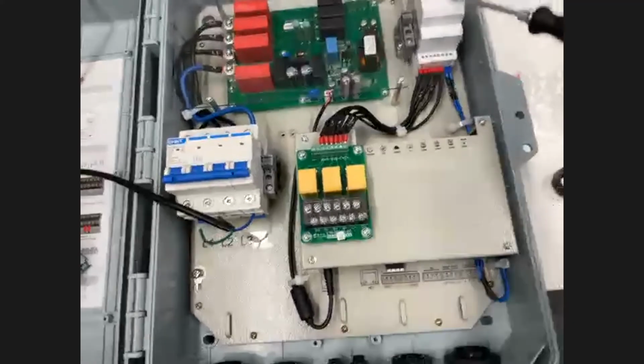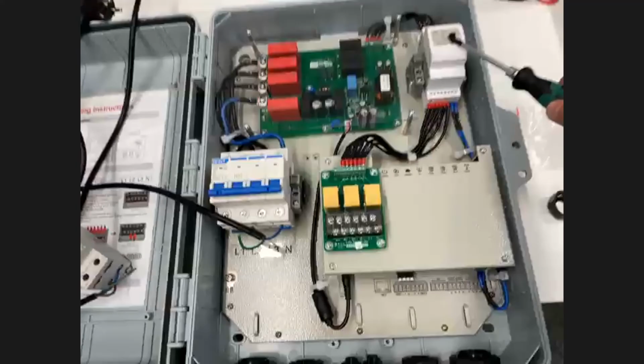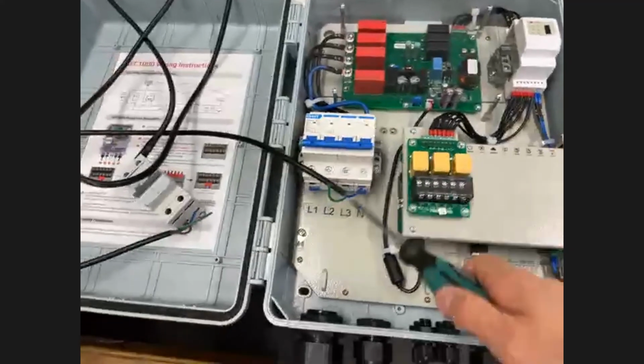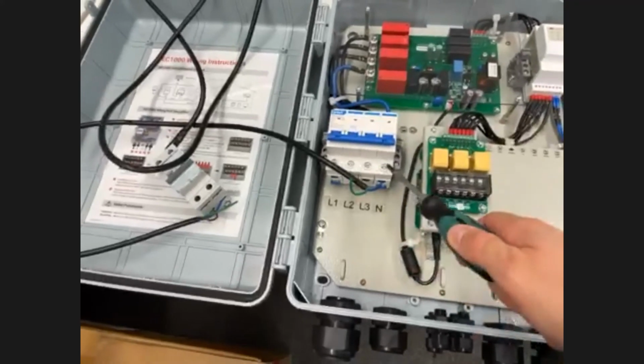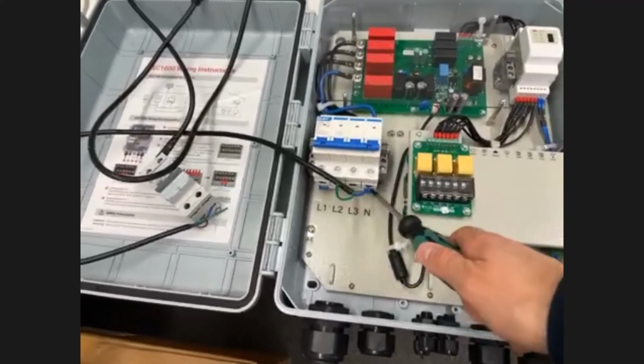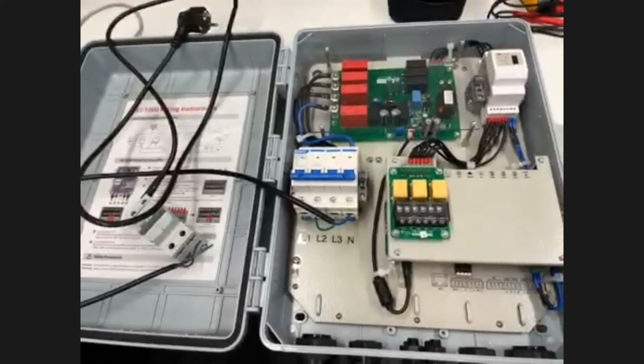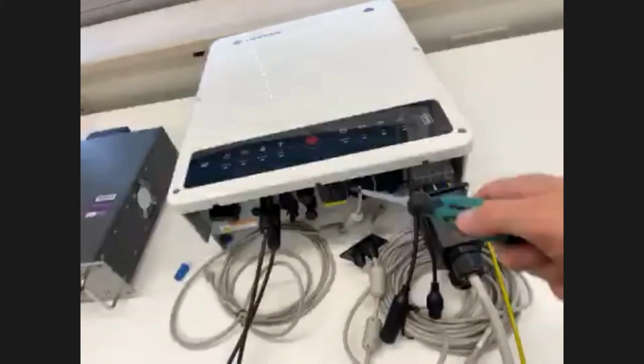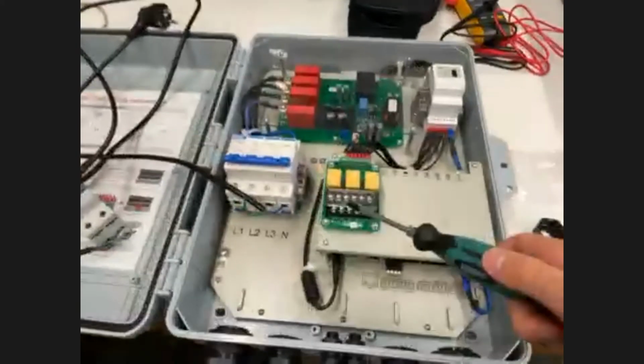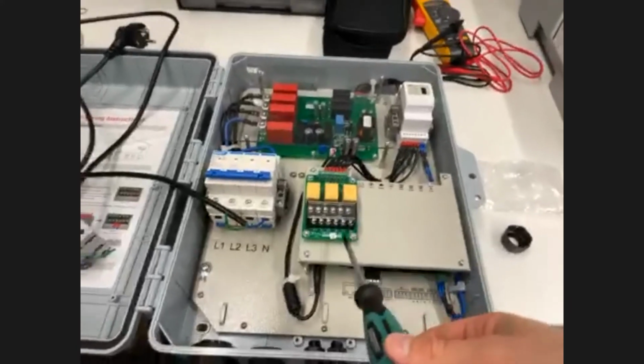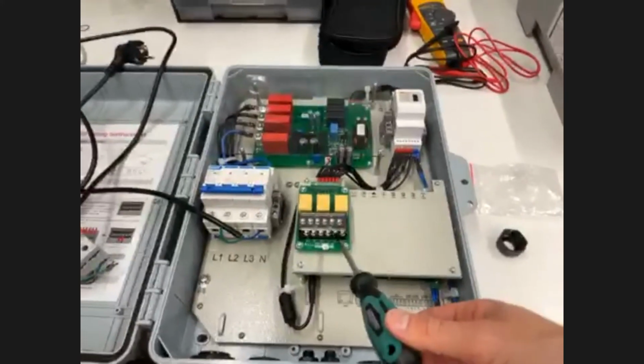You see it also has a smart meter here. Here you have the AC connection for the voltage sense. Here you need third-party CTs, you're not allowed to use the same CTs that are supplied with the smart meter here, those are only for direct connection to the inverter. For this one, you need third-party CTs with 5 amps on the secondary side, that's important.